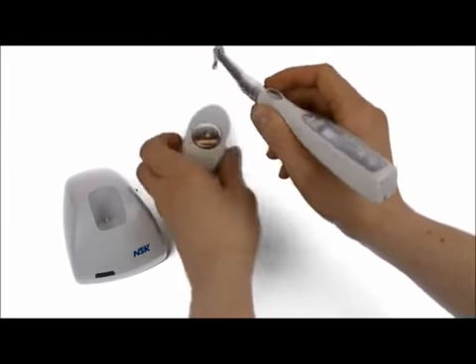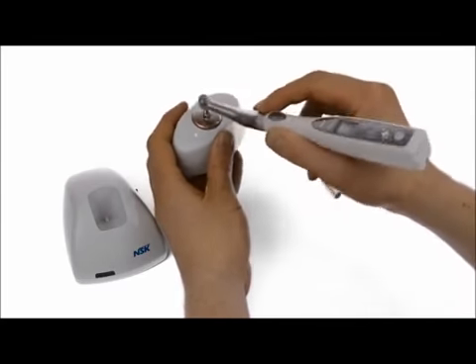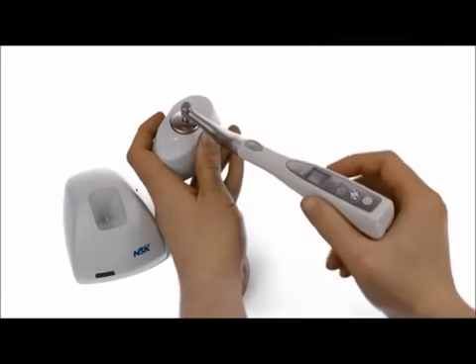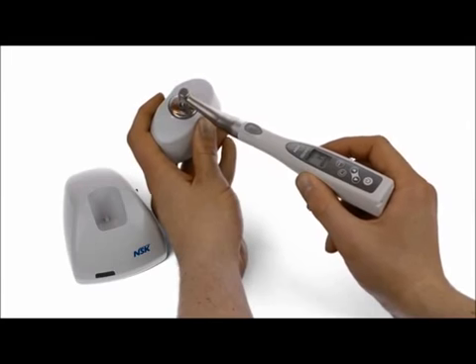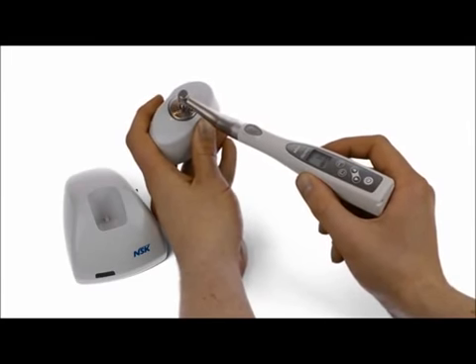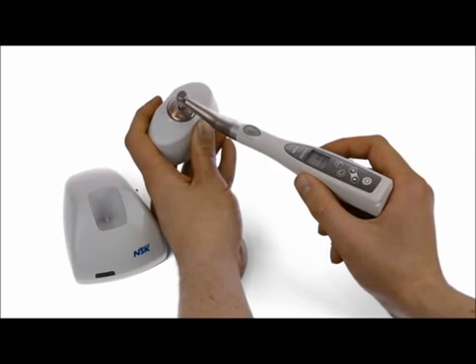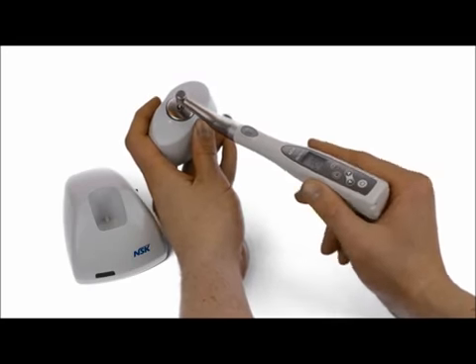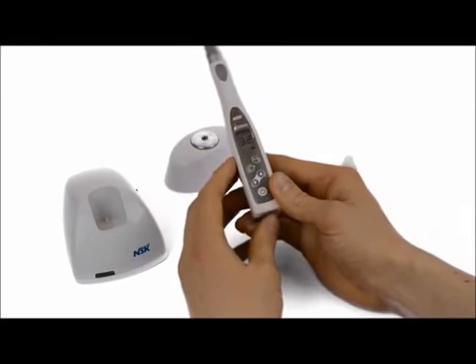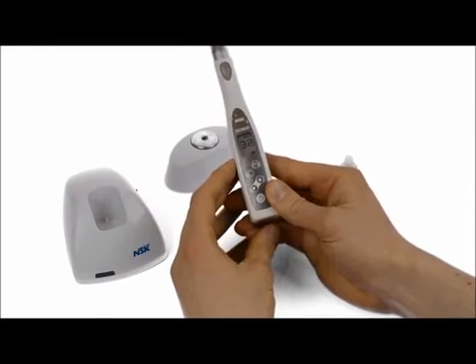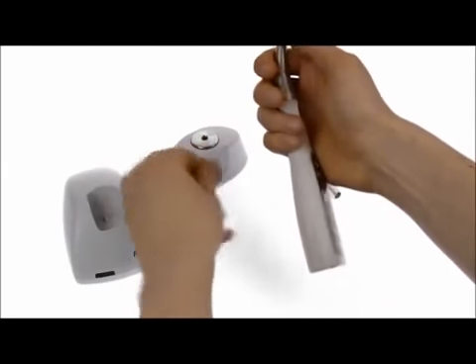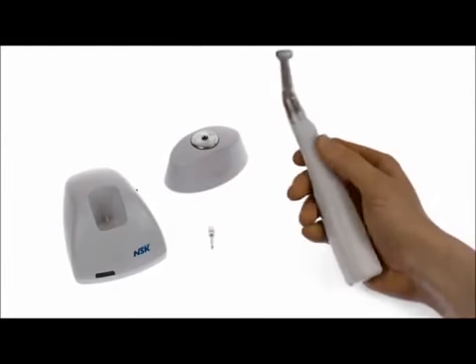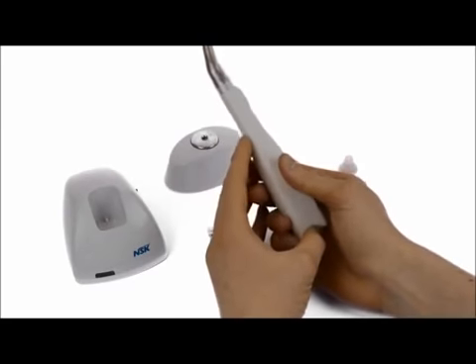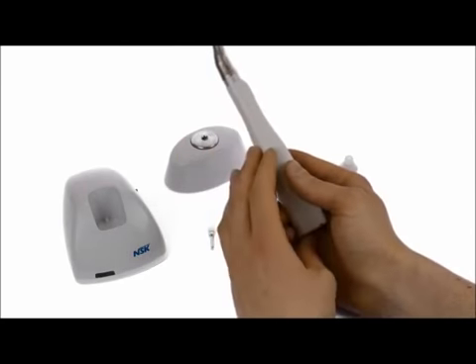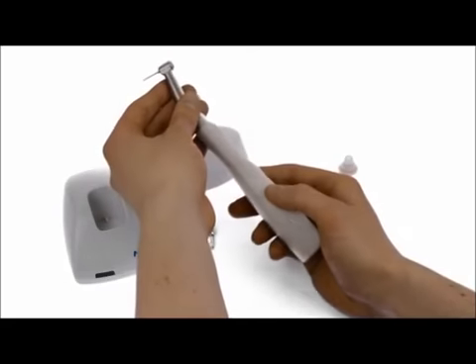So then what you do is take the handpiece with the calibration unit, insert the burr into the calibration unit like so, one press on the button, and hold the handpiece and the calibration unit tight as it will begin to rotate. Once this phase is finished and it's calibrated, you'll hear a double beep, and that means it's been a successful calibration, and you're good to go. So then you can disconnect the calibration burr and then put in whatever prosthetic burr you have. So long or short, they're all latch grip connections, and all the implant companies do such restorative burrs. So you don't need an individualized torque wrench for each implant company. You just need to get the different burrs.